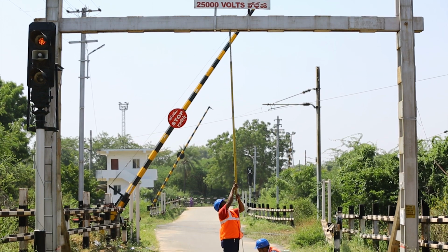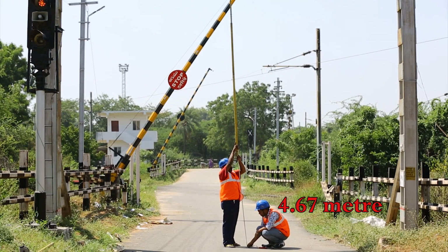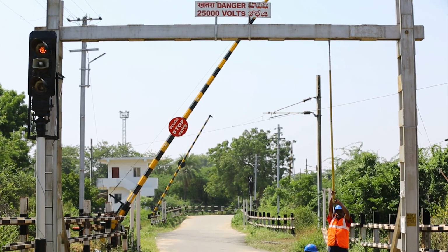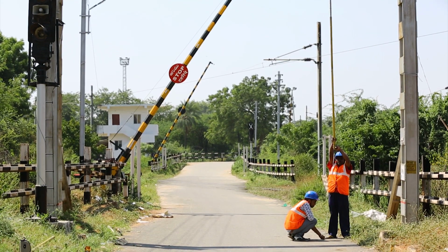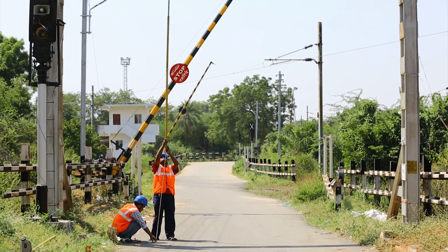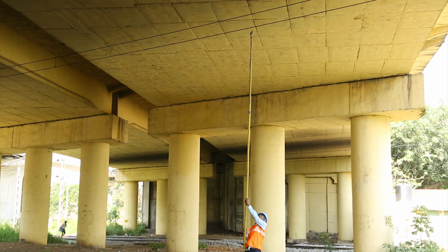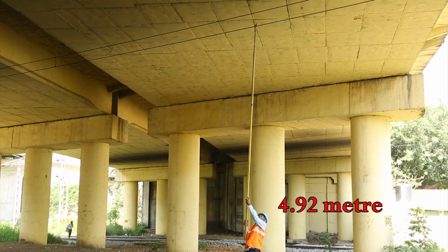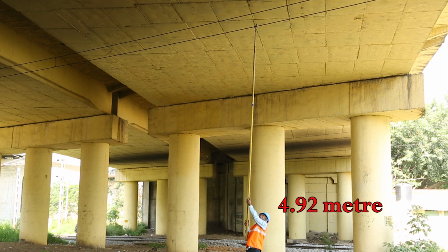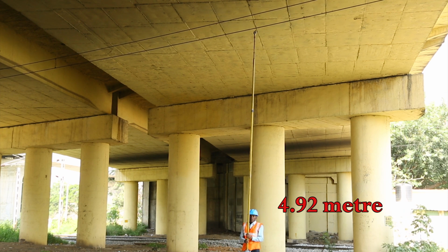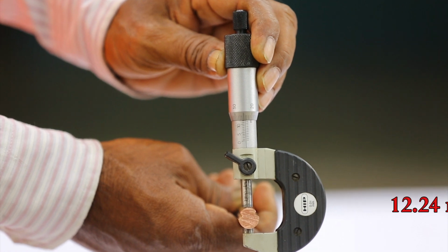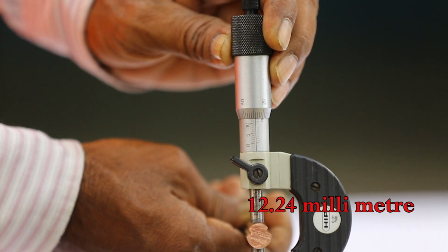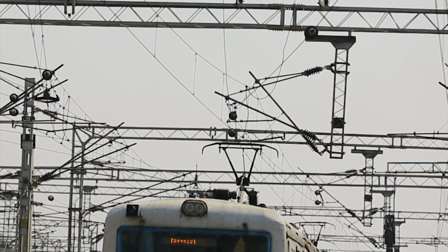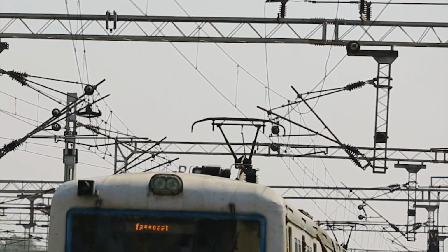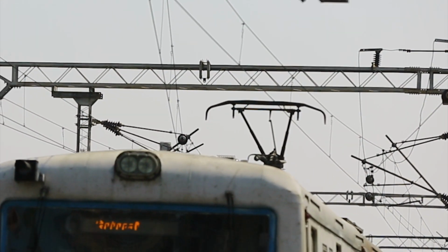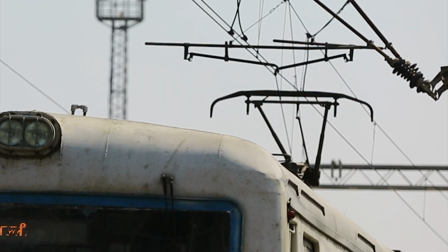Height of the height gauge at level crossing 4.67 meter. The minimum distance between the boom of height gauge and the ground should be taken as the height of height gauge. Minimum height of contact wire at overline structure 4.92 meter. Diameter of new contact wire 12.24 millimeter. Due to continuous swiveling and contact with the pantograph of electric locomotive, the diameter of the contact wire will decrease.